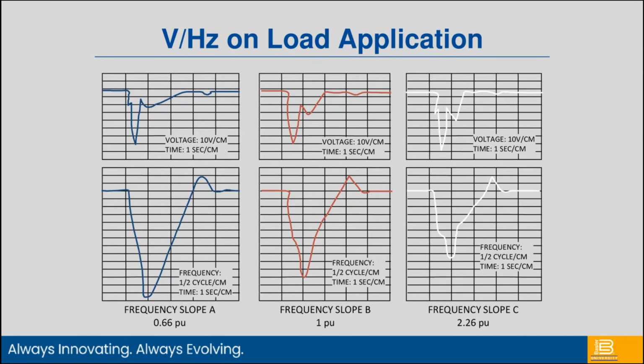The other thing it does is it can allow us to tune to load applications. So what happens in a machine as I add load onto it? Let's say I block load it. I put a large load on it, generator voltage drops, and generator frequency can drop. As generator frequency starts to drop, now I need more excitation to make the same amount of voltage, because I'm at a slower speed. So the voltage regulator will normally just increase excitation with zero limiters. I'm going to increase excitation to try to get my voltage back up. Well, if my prime mover already has this huge load on it, now I'm putting more excitation on it. I'm putting more flux on the rotor. Now I'm putting more electrical load that's inhibiting my prime mover from getting back up to speed. So I'm just putting more load on the machine when I'm trying to recover it.